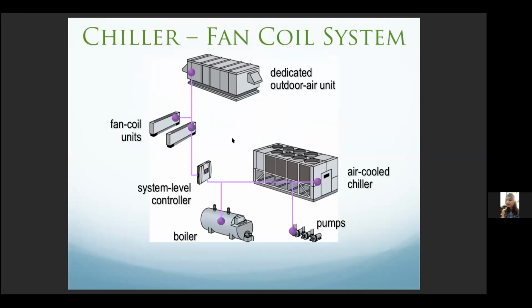Now we'll take a similar example for a chiller and fan coil system, where there's a dedicated outdoor air unit, fan coils, boilers, pumps, and a chiller. In this scenario, this is a pretty typical layout. A lot of apartment buildings are designed with such systems, where typically the fan coil units are in the apartments and they're left standalone, just to give you an idea.